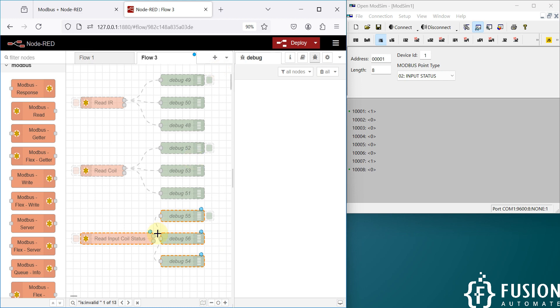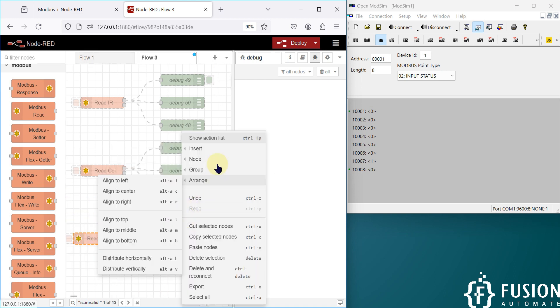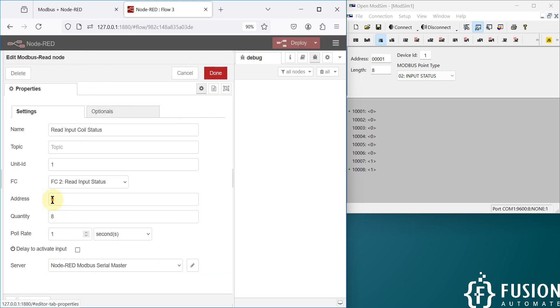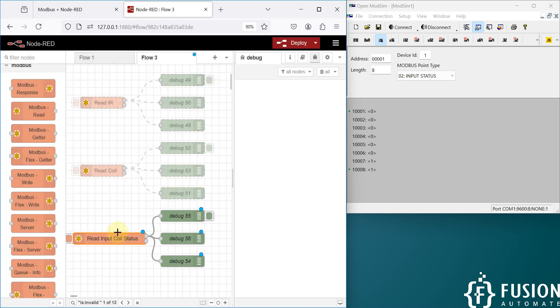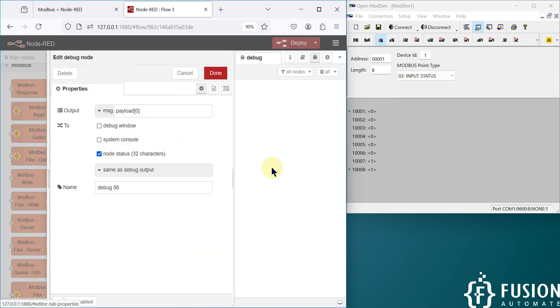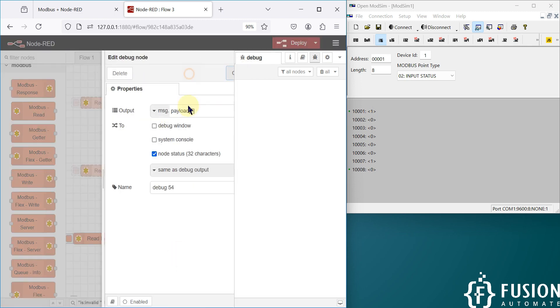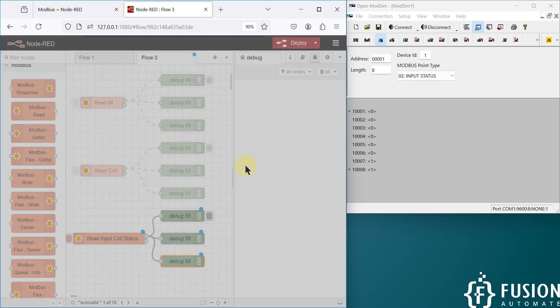Click 'Done' to save it. Now we will enable this node — right-click, then 'Enable Selected Node'. So we are going to read the input coil status from starting address 0, quantity 8, poll rate one second, and function code 2 for reading input status. This will read all input registers, the debug node will display all input register status in the debug window, and the node status will display the first and last input status.